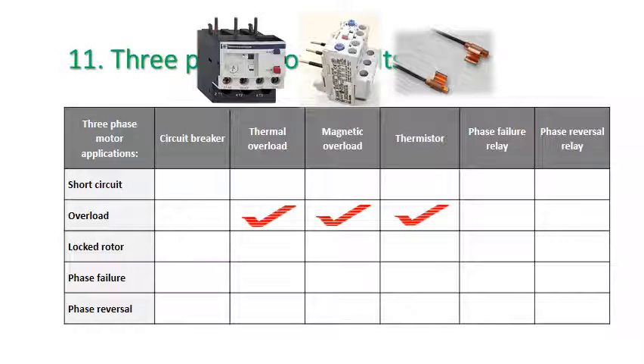The advantage of the bimetal overload is that, as we said before, it doesn't need special timing equipment to stop it from tripping out on motor startup, and it's simpler, it's cheaper to make, it's less to go wrong in there. The disadvantage is it has to cool down before you can reset it, and if you can imagine yourself in a factory huffing and blowing on a thermal overload to try and cool it down to get the factory going again while the workers stand around and look at you, it's probably not a good plan.